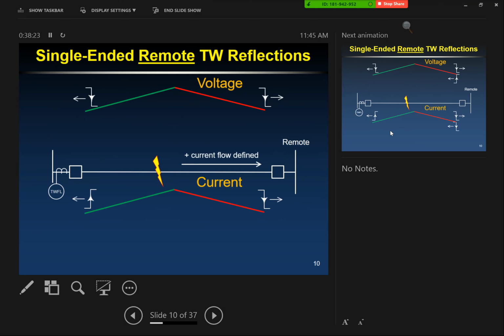Now, the remote end is a substation with multiple junctions off of it, with lower impedance, so we expect no current inversion, just voltage inversion. So that current comes back nicely off the remote end. Now we come to the fault, and we'd expect part of the current to reflect back, and part of it may travel through the fault. If that's a perfect short in a simple circuit...